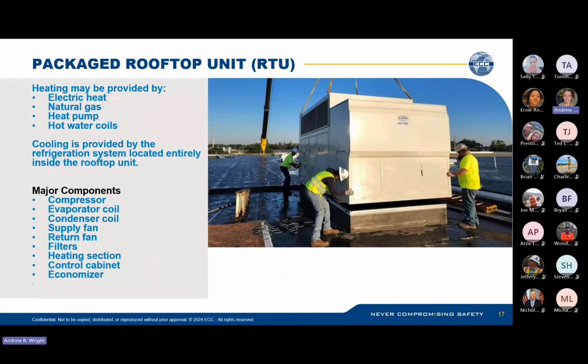With RTUs, the heating may be provided by electric, natural gas, heat pumps, or hot water coils. It doesn't really matter. The significance of the RTU is it's on the roof and it's a packaged unit, right? And it has the same components as other HVAC units: compressor, coils, condenser. It's just a larger version. One thing that may be different is a lot of them have something called an economizer, which is a set of dampers and sensors that uses the cool air outside to naturally cool the building, so it uses free cooling air to allow ambient cold air into the system, so that you're not always having to run your expensive compressors and everything.